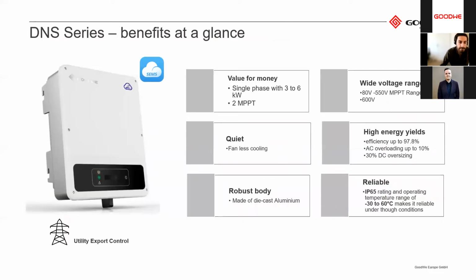If we go to our DNS inverter, it's sort of like a double XS, comes in the double size, or double AC output, also the double size, and has 2 MPPTs. The DNS has a quite wide voltage range, so it has a very low startup voltage at 80 volt. This means that it can start producing energy quite early in the day and also stop producing it quite late in the evening, so giving you that little extra energy yield in mornings and evenings. Apart from that, it's quite similar to the XS that we just talked about.